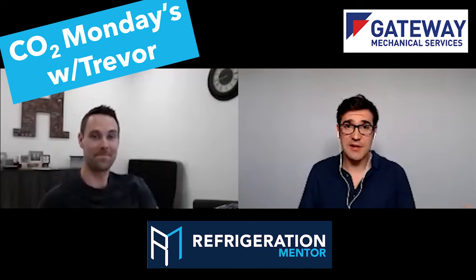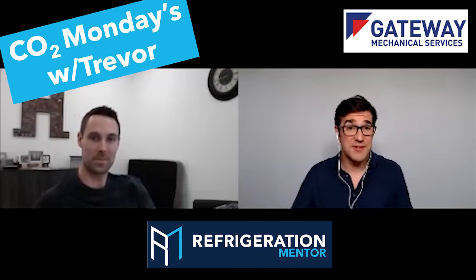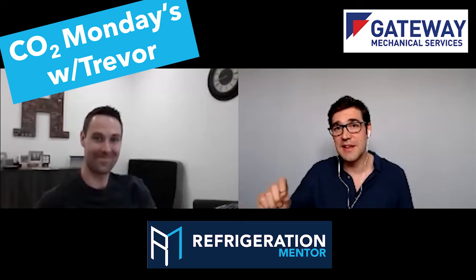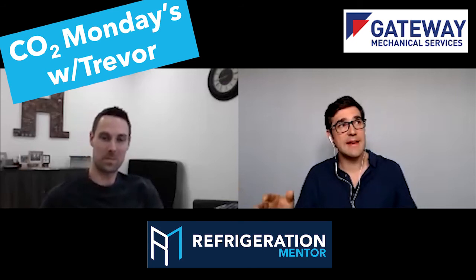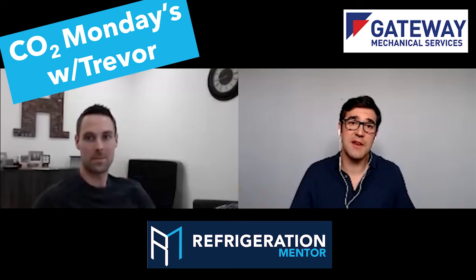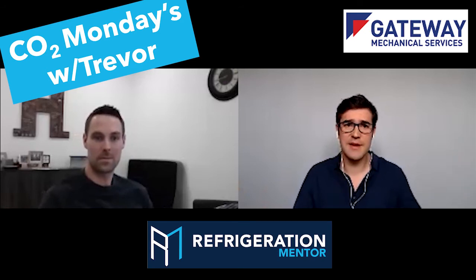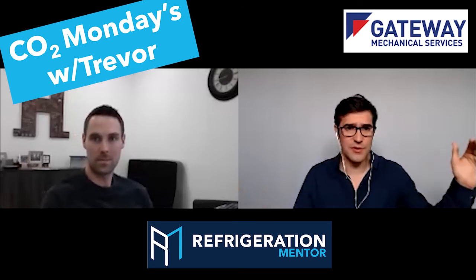We talked about you got three different defrosts from three different manufacturers that do the same thing, but they work three different ways. Understanding each one of these processes, the sequence of operation, is going to make that system run so much better. So when you do run into an issue, you know what to look for. Okay, well, we're tripping off on high head. My gas cooler is way too high. Look at the ambient outside. It's only 80 degrees outside, but we're banging off. What is the problem? Is my high pressure valve opening and closing properly? Let's go look at that.